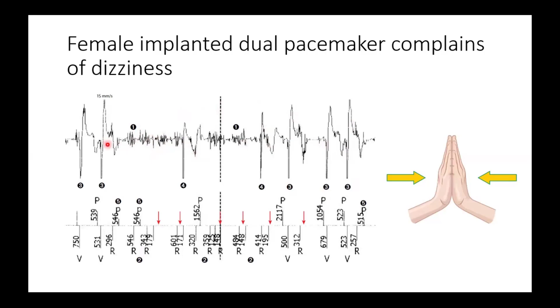So how can you overcome this problem, Sasi, by programming? First, you should evaluate the sensing polarity. Here, the sensing polarity was unipolar, so we program it to bipolar, and the problem is solved. Another thing: if the problem is myopotentials, bipolar programming will solve it. However, if it's a matter of noise in the lead, we should consider evaluating the integrity of the lead, and if the patient is pacemaker dependent, we may consider replacement of the lead with another one.